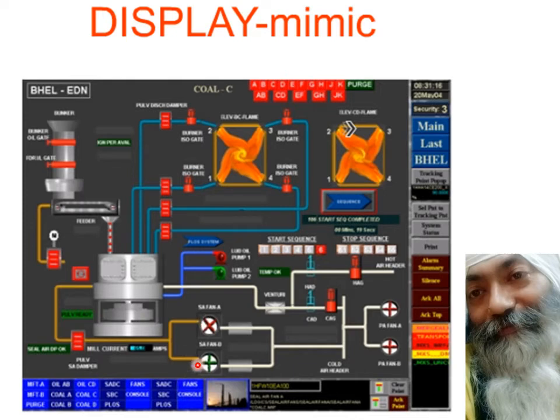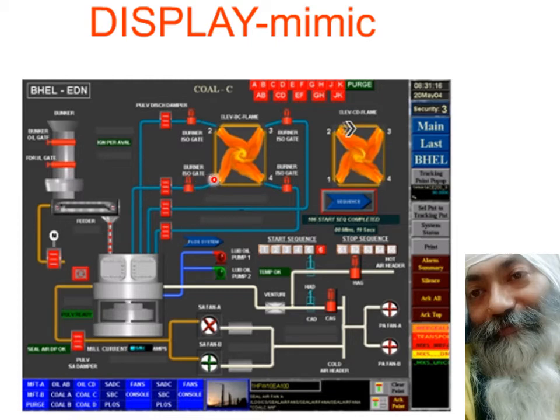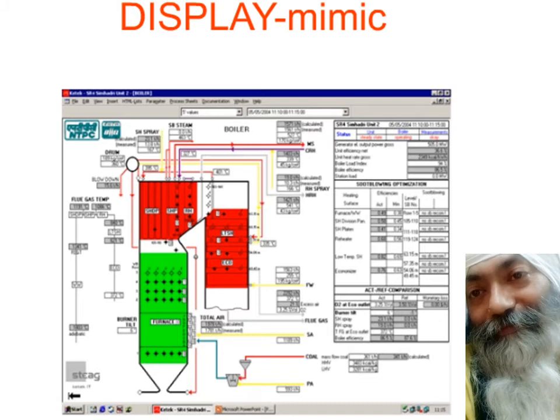From the mimic you can switch on, switch off, or change the speed of fans and pumps. Everything physically present in the plant is shown in the mimic — a hopper feeding coal onto a conveyor belt, which carries it to a pulverizer, where the powdered coal is blown with air and fired in the boiler. Each component on this page can be individually controlled, and this is just one of many pages.